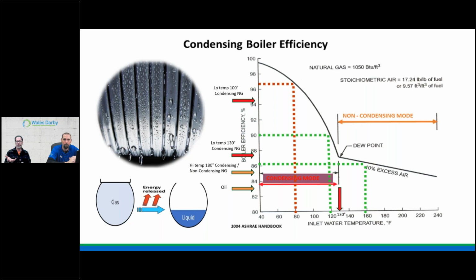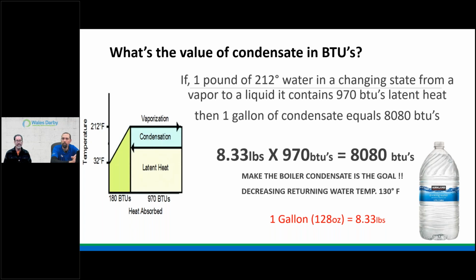So here, just kind of showing you, if you're in the efficiency game, or if you think you're selling high efficiency, but you're not understanding the backstory, the true story, right? Lowering water temperature, today might be day one for you. Yeah. So here it is, that latent heat, the changing of a vapor to a liquid. And this is where we capture a good bit of BTUs that would normally just be leaving the building. So without understanding and achieving how we get this thing to condense, well, all right, so here we go. Lowering water temperature starting at 130, the lower you go, the better the efficiency. We got that, right? So now we have this great liquid coming back, this condensing, collapsing flue product to a liquid crossing over our heat exchanger.